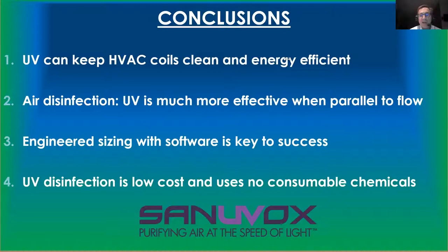And there's a sign on that door saying that there are some UV lights and do not get inside if UV lights are on. But what you're putting this on is basically to tell the operator not to force the switch and turn on the lights when he's inside. But typically, and it's in our installation recommendation, and Scott knows that he's installed many systems, there's always a safety switch that cuts off all the lights when you want to walk into the air handler.